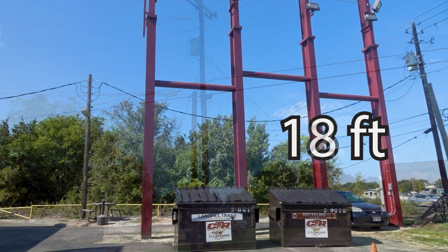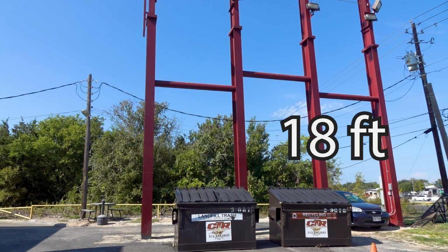Where the space under the conductors is wide enough to allow for vehicular traffic, such as a residential driveway that is not subject to truck traffic, the clearance must be at least 12 feet above the finished grade. And where the conductors cross over commercial property or a right-of-way that is subject to agricultural equipment, such as mowers or truck traffic, the clearance must be at least 18 feet.